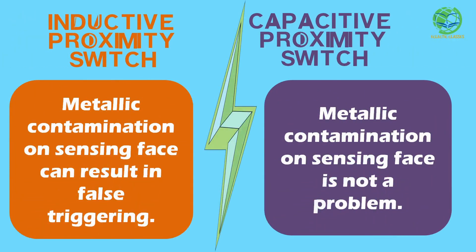In case of inductive proximity sensors, metallic contamination like iron filings on the sensing face can result in false triggering, while the same won't result in false triggering in case of capacitive sensors.